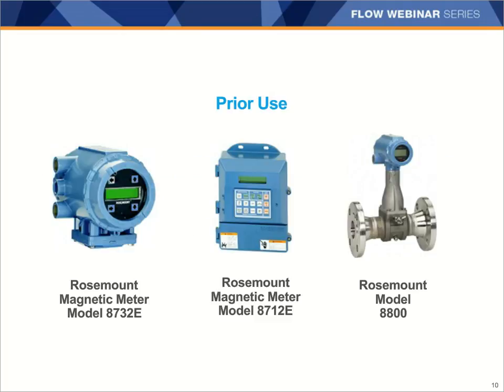Emerson offers magnetic flow meters with the 8732E and the 8712E, as well as 8800 vortex meters for prior use applications. To make the documentation process easier for you for these devices, we actually have a hardware assessment that has been provided by Exida. The hardware assessment consists of a FMEDA, which is failure modes, effects, and diagnostic analysis, to help determine the fault behavior and the failure rates of your device. These are then used to calculate the safe failure fraction, or SFF, and the average probability of failure on demand, or PFD. This assessment actually provides the safety instrumentation engineer with the required failure data per IEC 61508 and 61511.